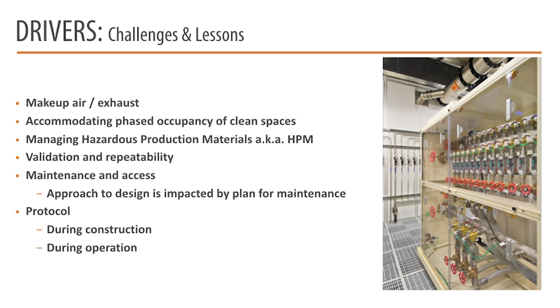It's really twofold. When you start constructing a new building, you build a shell, and eventually get down to building a clean envelope where the clean room is. From there, you progress to activating air handlers with temporary filters, and finally to a condition that simulates being done and ready for the owner to move in. You start from a dirty environment and progressively apply cleaning protocol as a contractor to get to that end game.